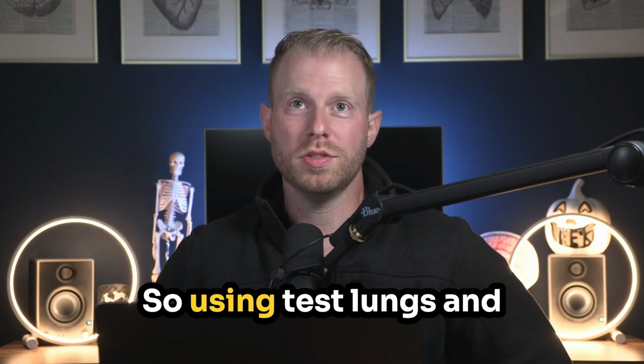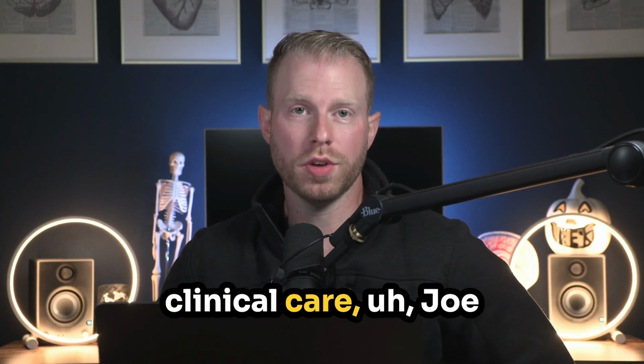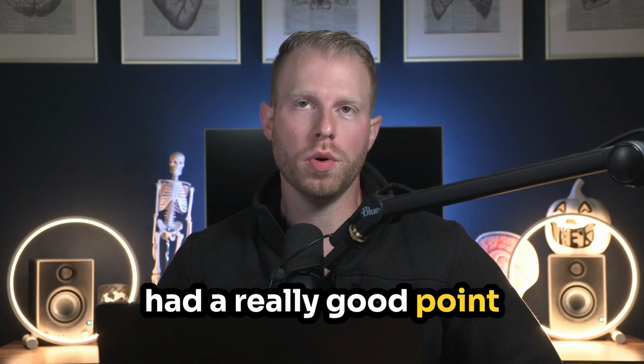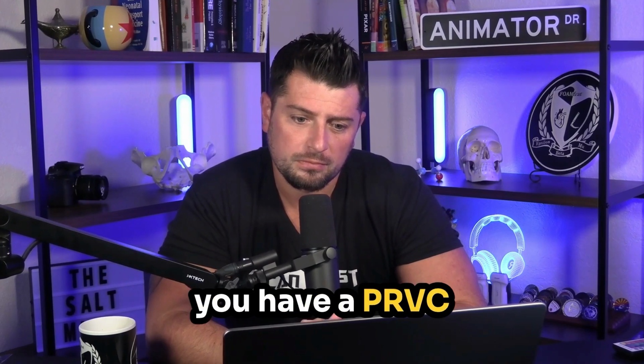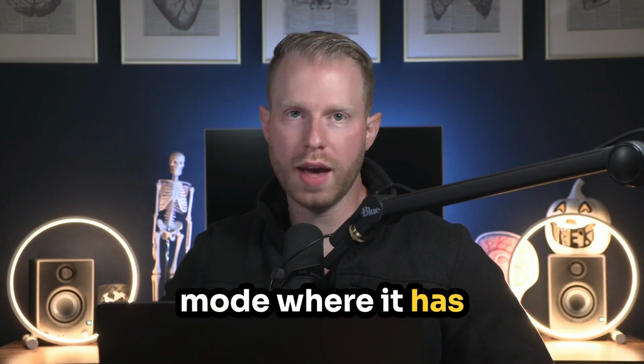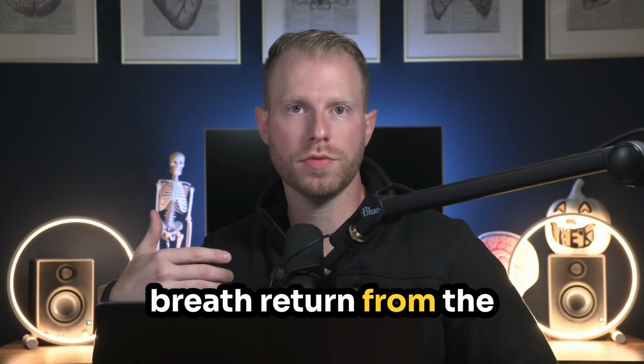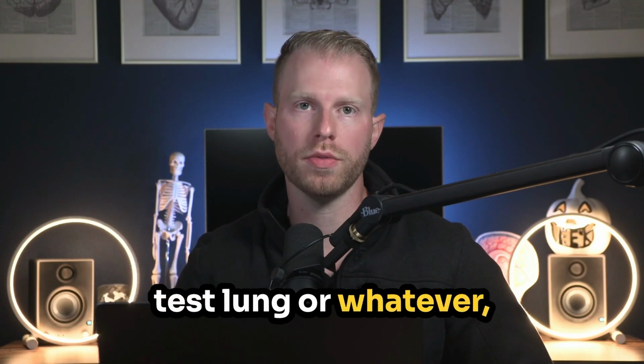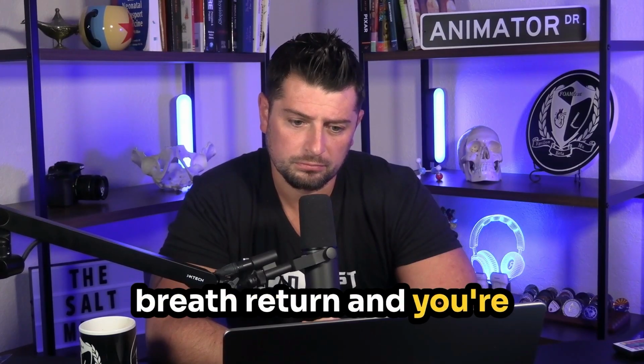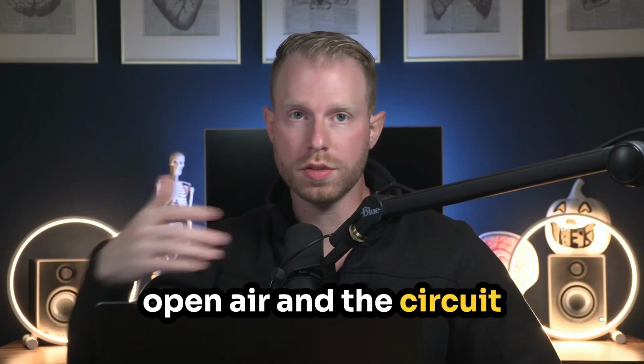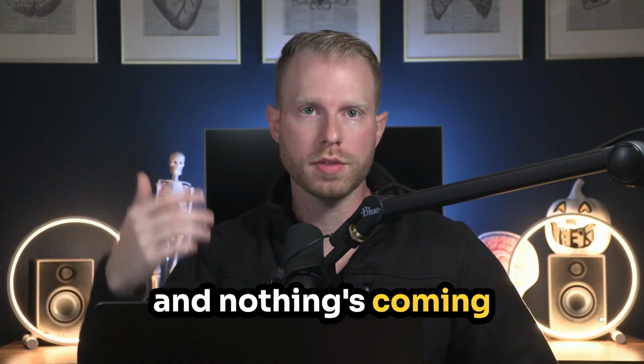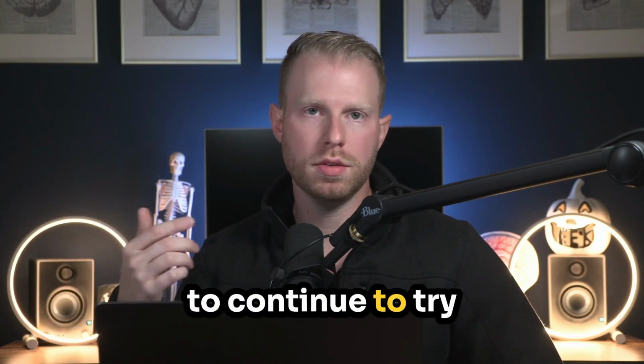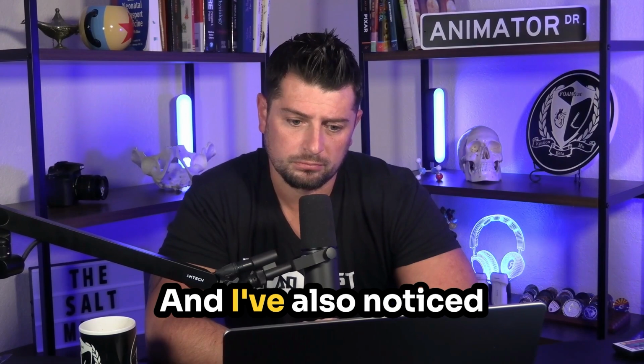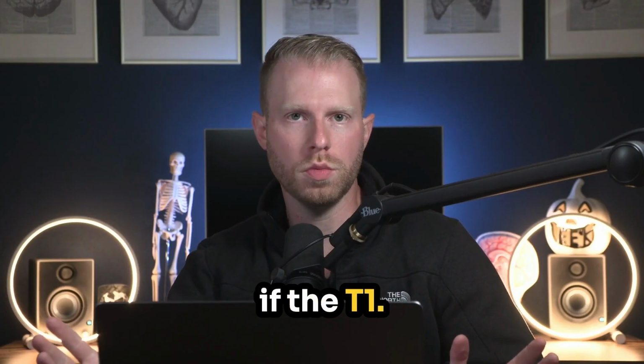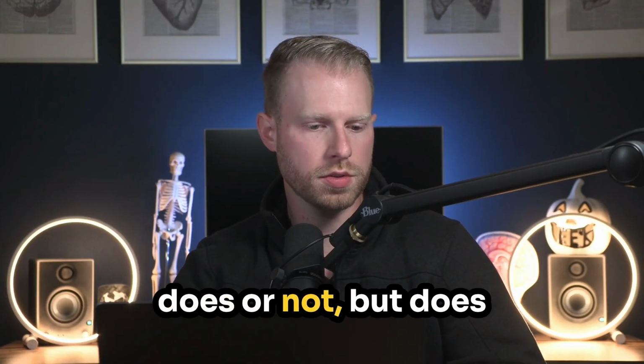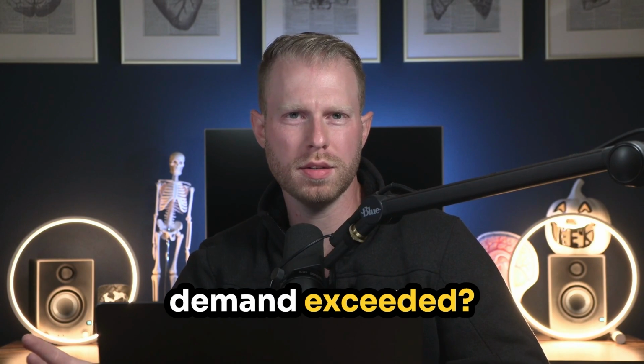Yeah, so using test lungs in clinical care, Joe had a really good point: if you have a PRVC mode where it has to have some type of breath return from the patient or from the test lung, and it doesn't have that breath return and you're just venting into the open air, and the circuit pressure is zero and nothing is coming back, it's going to continue to try to figure out what's going on. And I've also noticed, I don't know if the T1 does this, maybe you could tell me, but does it ever hit a blower demand exceeded?